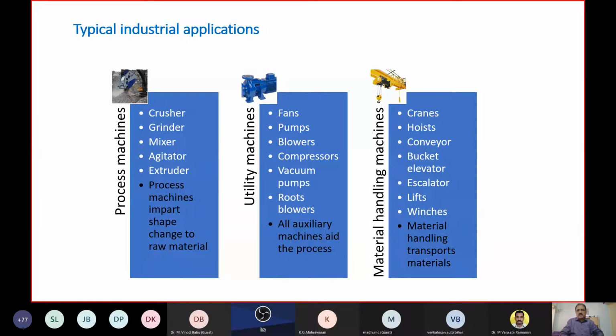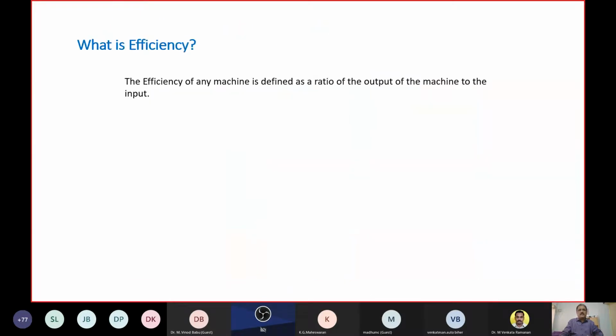66% of the total power consumption is through utility machines or auxiliary machines, which are largely centrifugal in nature. And the third and last application area for industrial motors is material handling or transport machines, where we use cranes, hoists, conveyors, bucket elevators, escalators, lifts, winches, and so on. So these are applications where motors are used, and between material handling and process, approximately 33% would be the total energy consumption fed through the motors. So 66% is accounted for by utility machines, and therefore our thorough understanding of the opportunities available for energy saving through utility machines, either through optimization or through higher efficiency or through adopting speed variations in order to optimally meet the process flow, will be important.